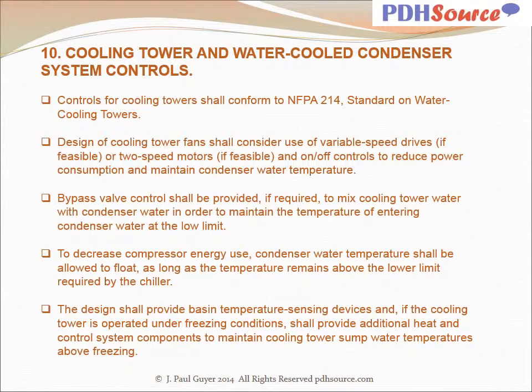For cooling towers and water-cooled condenser systems, controls for cooling towers shall conform to NFPA 214, standard on water cooling towers. Design of cooling tower fans shall consider use of variable speed drives if feasible, or two-speed motors if feasible, and on-off controls to reduce power consumption and maintain condenser water temperature. Bypass valve control shall be provided if required to mix cooling tower water with condenser water in order to maintain the temperature of entering condenser water at the low limit.